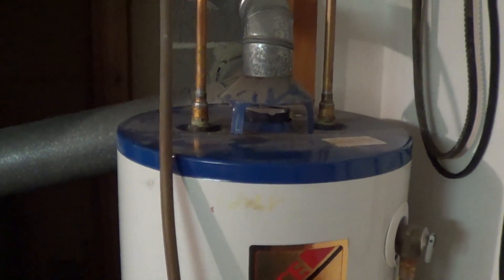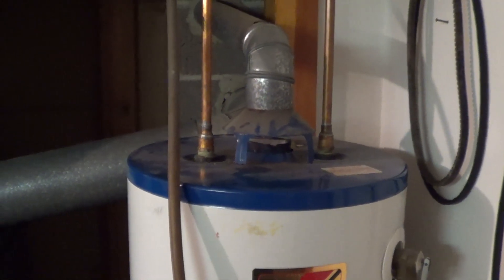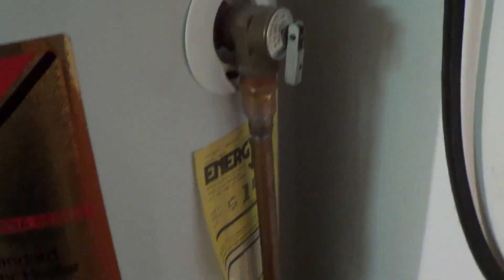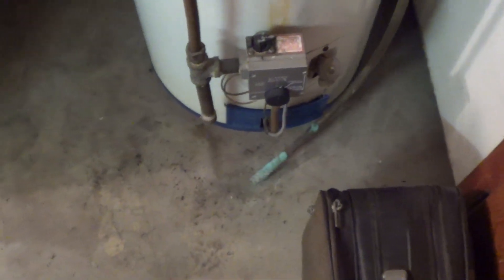That tells me this water heater was at least prepared for shipment sometime around February of 1980, and therefore it has been in service longer than I have been alive by approximately two years. But as you can see, if you look at the base of the tank, the parts that can be readily seen — and I believe the other parts as well — are rust-free and undamaged. The only sign of leakage is from the pipe leading down from the pressure relief or blow-off valve in the side of the water heater.